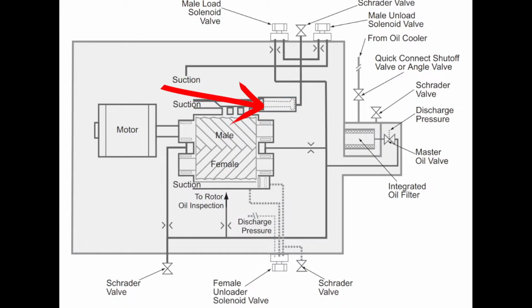If the slide puck is all the way out to the outer surface, close to the discharge, that is an unloaded slide. And if it's further back into it, which is a lot of times what will happen, they'll get stuck back in here, then it is in a partially loaded or loaded position at that point, which in the field, if you're having to do a repair like that, you always end up having to reach in there with a set of pliers or something and pull that slide back over to you so that you can get to it, service it, and do what you got to do.